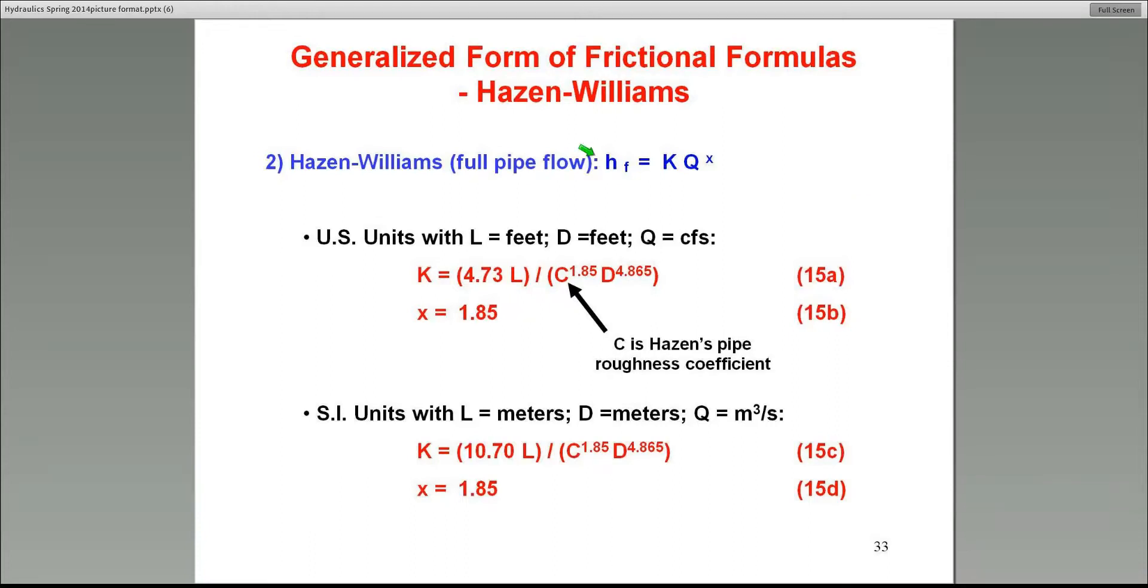Primarily because this Hazen roughness coefficient can be fixed or held constant with minor adjustments for the pipe flow velocity. Now, Hazen-Williams is the same type of equation in the same form, where K is equal to 4.73L divided by C to the power 1.85 D to the power 4.865. Make sure you calculate this very carefully for each problem because I do not have a physical interpretation of K. Therefore, we do not know if we got it right or wrong. L is the length of the pipe in feet. C is the Hazen's roughness coefficient. I'll show you a table. You can get it from there. And D is the pipe diameter in feet, not in inches, but in feet. The exponent, don't forget, is 1.85.